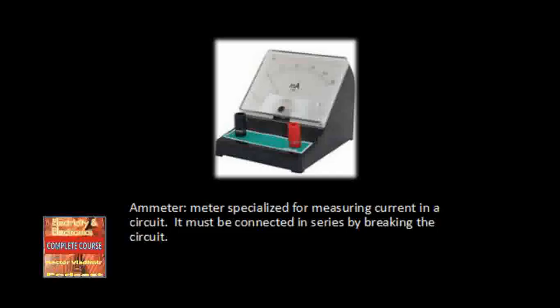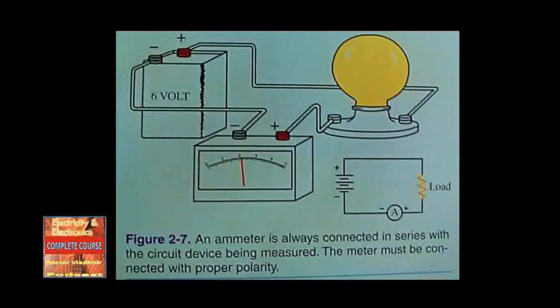Section 2.2: Ammeter. An ammeter measures electrical current in a circuit, usually in amperes, milliamperes, or microamperes depending on the scale design. The coil in the ammeter is wound with many turns of fine wire. If a large current is allowed to flow through this coil, the ammeter will quickly burn out. In order to measure larger currents, a shunt or alternate path is provided for most of the current. Most of the current flows through the shunt, leaving only enough current to safely work the ammeter movement coil. The shunt is a precision resistor connected in parallel with the ammeter coil.